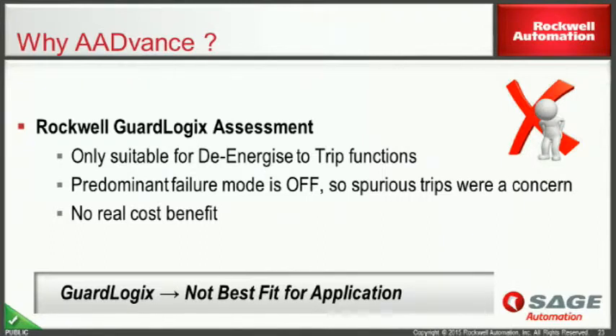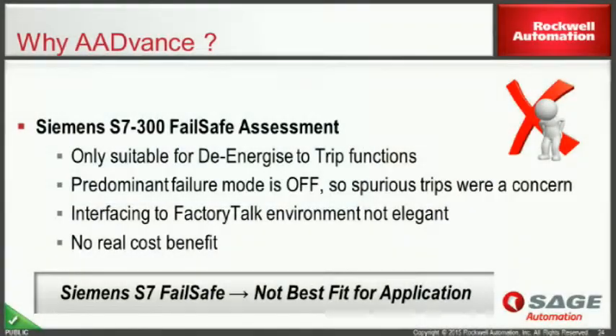The predominant failure mode is off. That type of controller looks for any reason to shut down. So we were concerned about spurious trips. And also there was no real cost benefit in terms of hardware between GuardLogix and AADvance. Siemens, our assessment was quite similar to the GuardLogix, except the additional one is interfacing to the FactoryTalk environment wouldn't be elegant. Siemens talking to Rockwell, it's like Ford and Holden. It just doesn't go together very well.